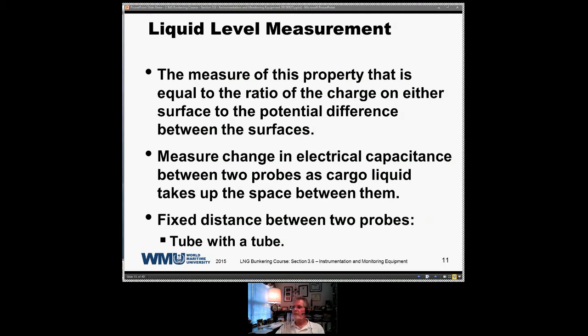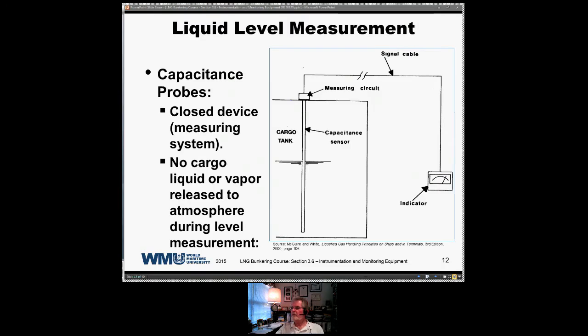This is a very, very simple diagram of the capacitance sensor, tube within a tube. It goes into your electronics, and it's transferred over to an actual level indicator. There's no cargo, liquid, or vapor released to the atmosphere during the level measurement, all enclosed inside the tank. So nothing ever comes into contact with the outside.